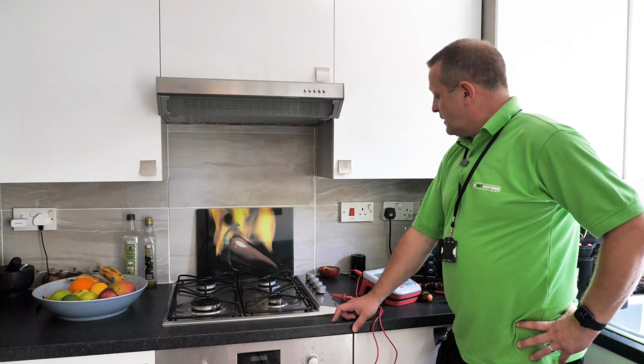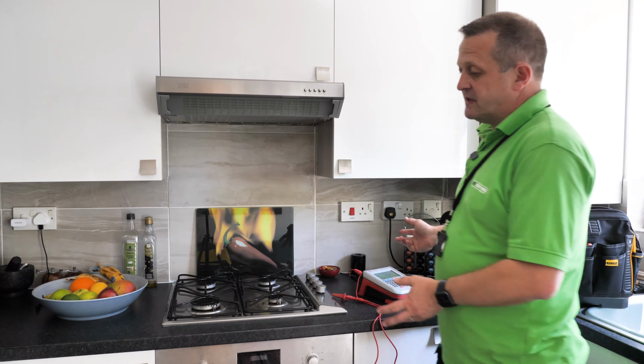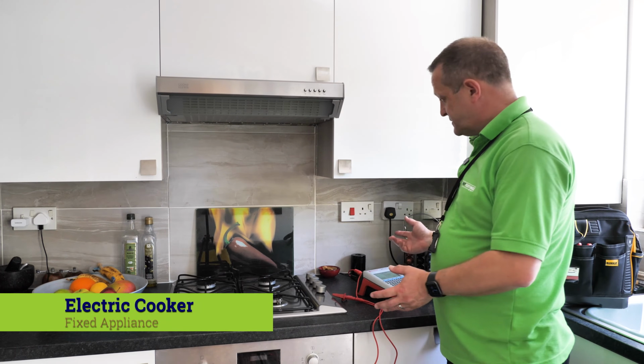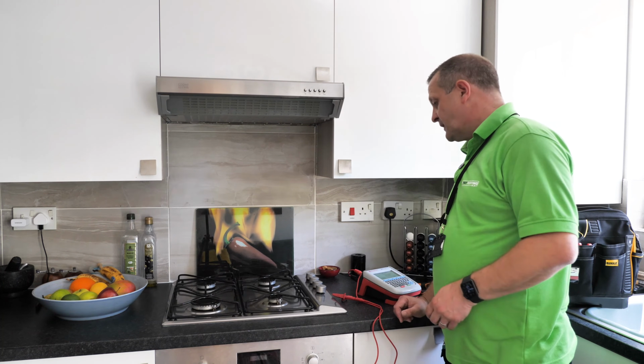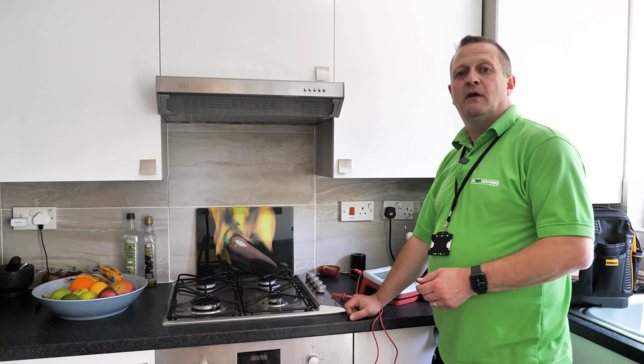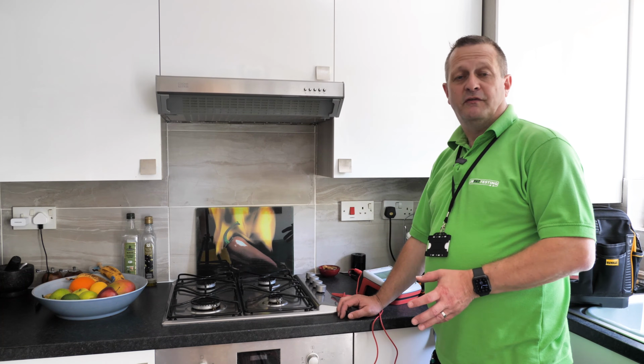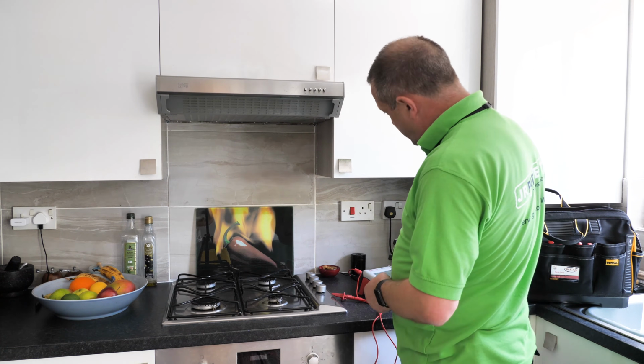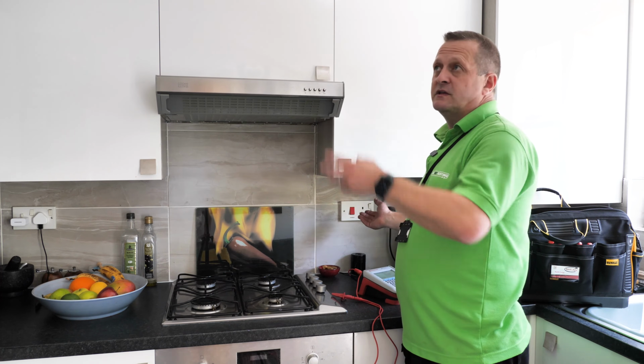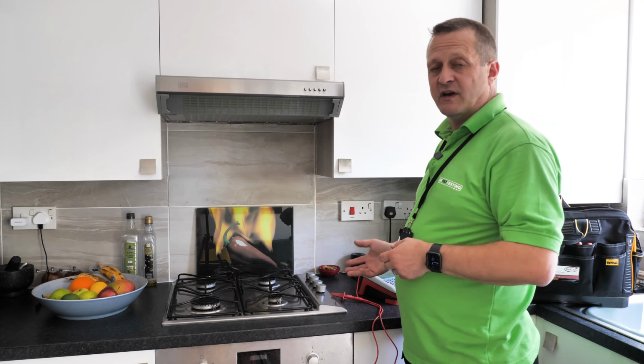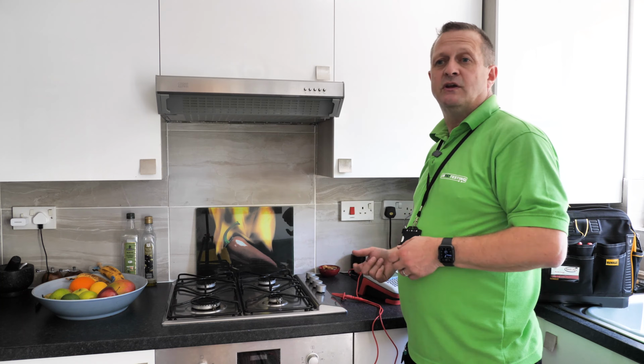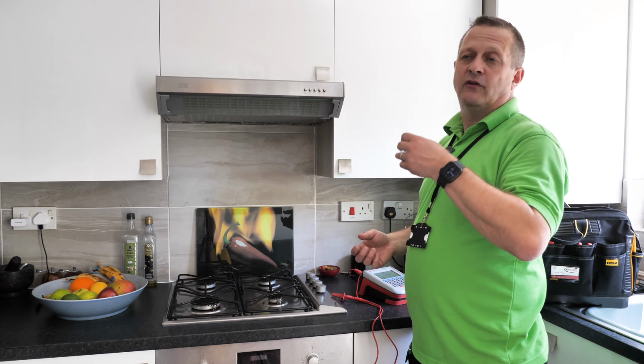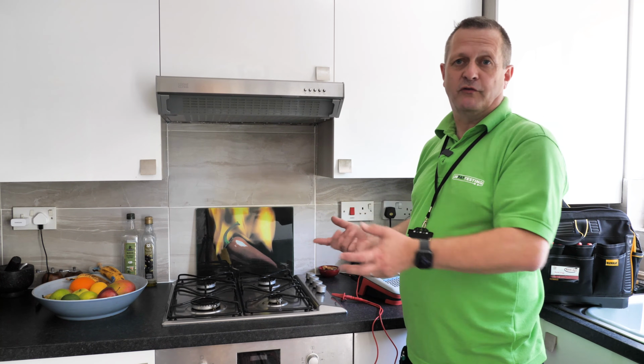Right, so now we're going to be looking at testing a class 1 fixed appliance such as this cooker, and we're going to be doing it as per the correct method in the 5th edition. The first thing that we need to do before doing anything is making sure that we have got the appliance isolated at the consumer unit. So we're just going to quickly go and sort out the consumer unit and lock the fuse off.